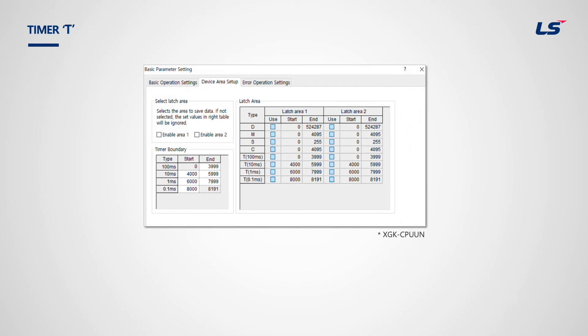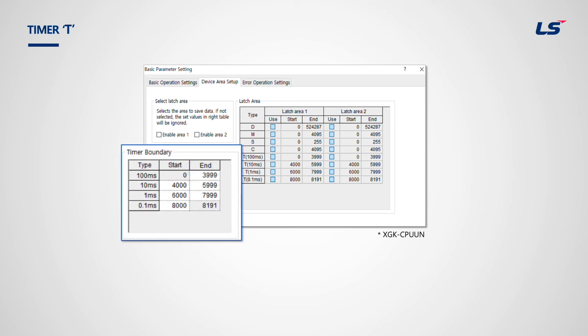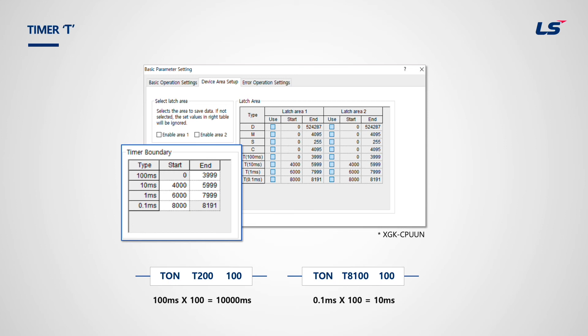This is the timer. In basic parameter settings, the second tab, device area setup, has timer boundary on the lower left. 100 milliseconds contains numbers from 0 to 3999, meaning device addresses T0 to T3999 have a timer value of 100 milliseconds. For example, timer address T200 lies between T0 and T3999, so its timer value is 100 milliseconds, meaning a set value of 10 equals 1 second.